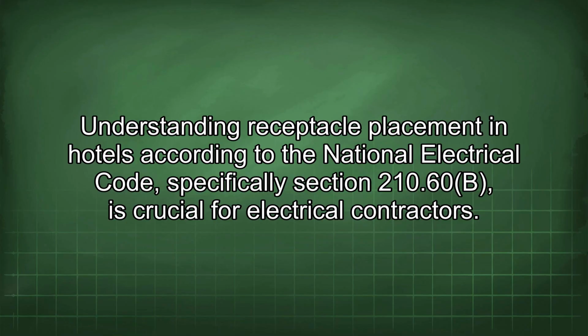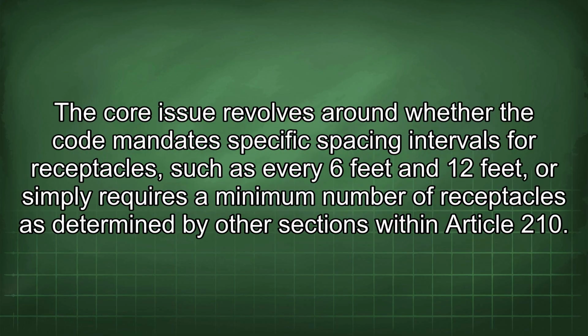Understanding receptacle placement in hotels according to the National Electrical Code, specifically Section 210.60b, is crucial for electrical contractors. The core issue revolves around whether the code mandates specific spacing intervals for receptacles, such as every 6 feet and 12 feet, or simply requires a minimum number of receptacles as determined by other sections within Article 210.